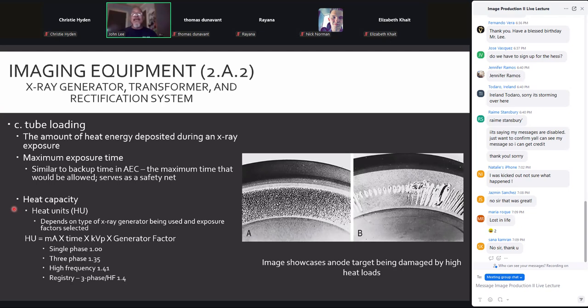When we go to three phase and high frequency, the registry has combined those into a generator factor of 1.4. Technically, a three-phase 6-pulse generator is a 1.35, and a high-frequency generator is a 1.41 as far as generator factors go. But again, the registry has put those together, and we're using 1.4. So essentially what we're saying is that a three phase or high frequency generator will generate 40% more heat units per exposure than those same technical factors will on a single phase generator.